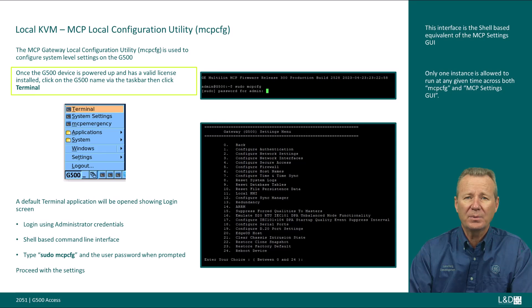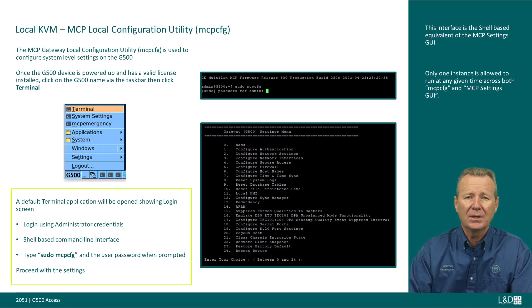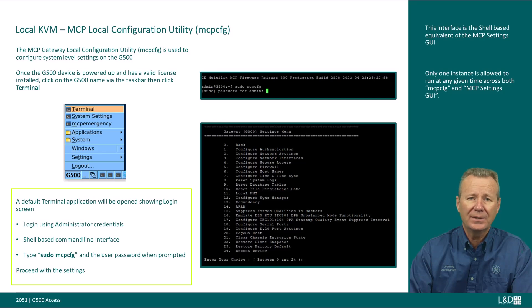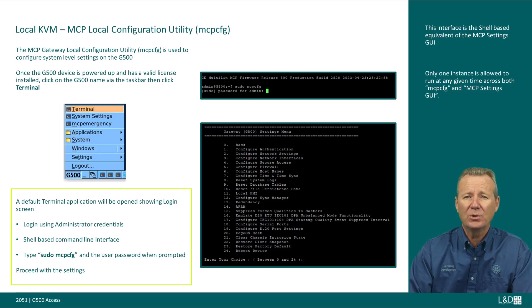Once the G500 device is powered up and has a valid license installed, click on the G500 name via the taskbar, then click Terminal. A default terminal application will open showing the login screen. It's a shell-based command line interface. Log in using administrator credentials, then type sudo mcpcfg and enter the user password when prompted. A gateway settings menu will be shown and you can proceed with the settings.